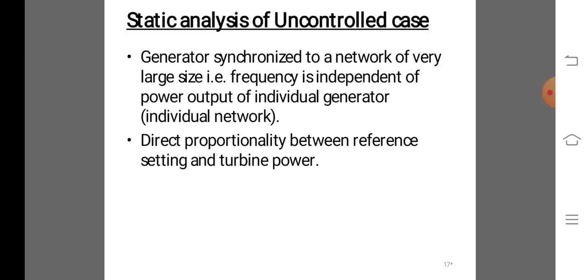They are connected for system operation, for perfect system operation condition, including the steady state. To maintain this, AGC will adjust the power reference value of the generators. It has to participate in the automatic governor control.